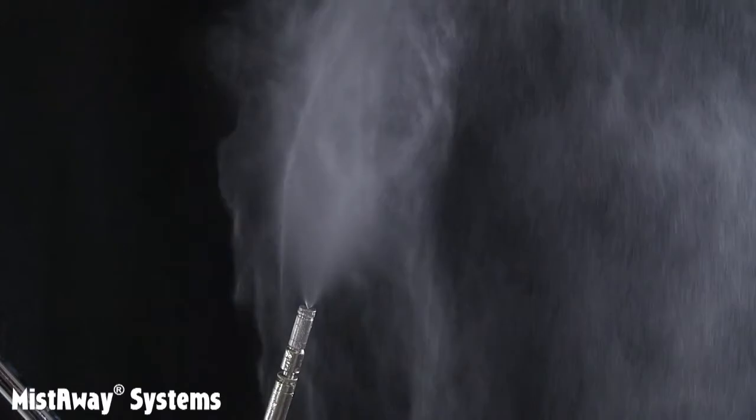Okay, so we've established that it's really important for the pressure in the line to decay quickly when the pump shuts down so that the nozzles don't stream or drip. And we accomplish that by putting an auto drain valve in the line. But what happens after the nozzles close?